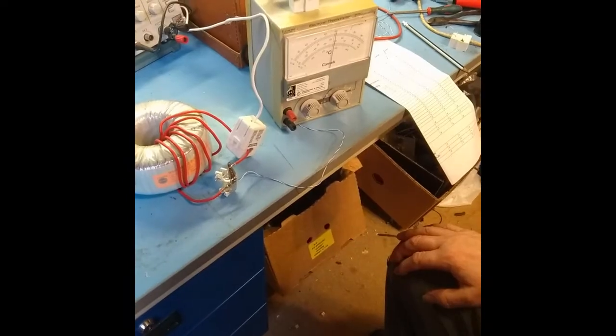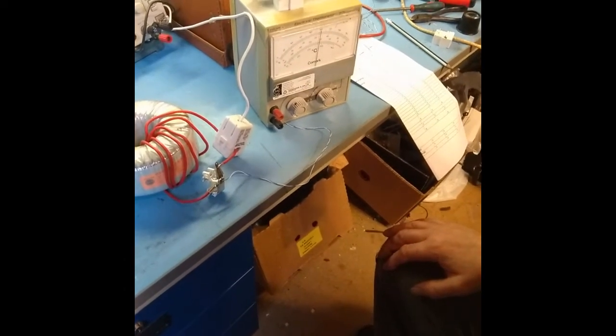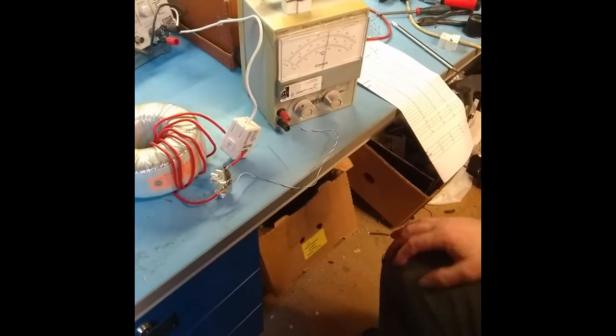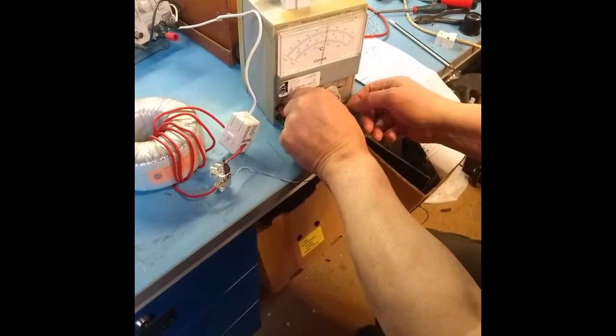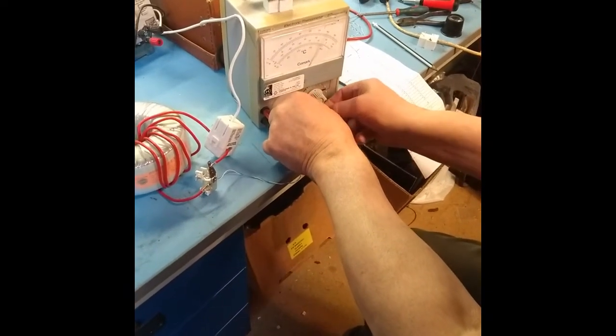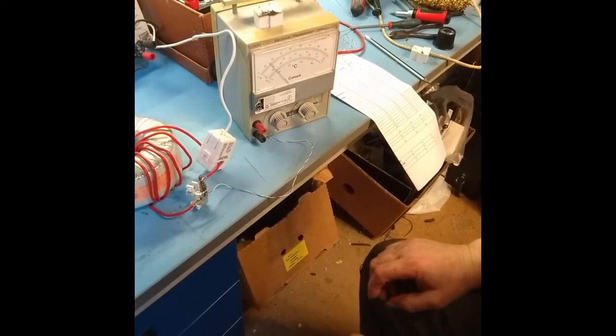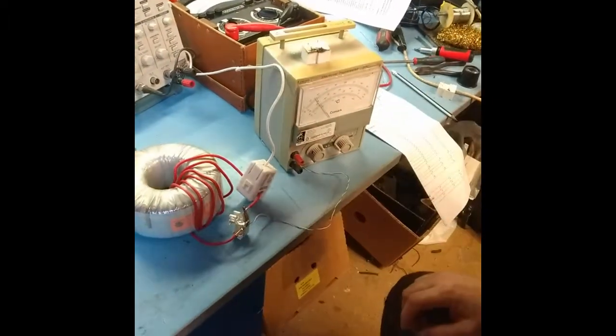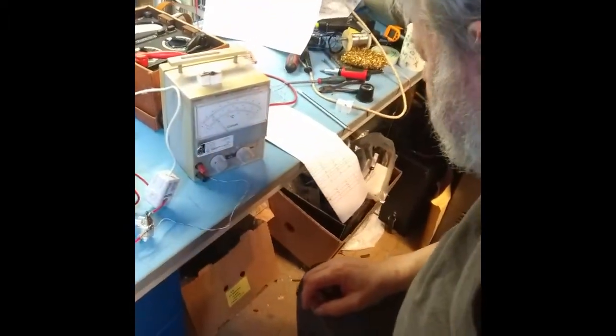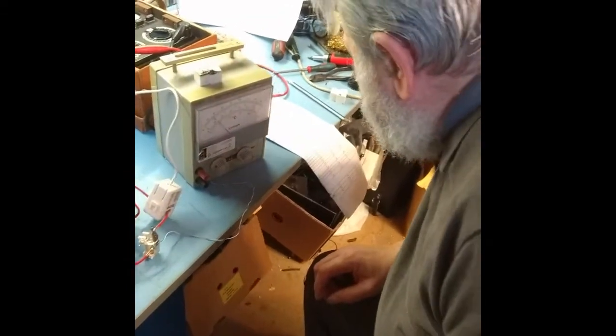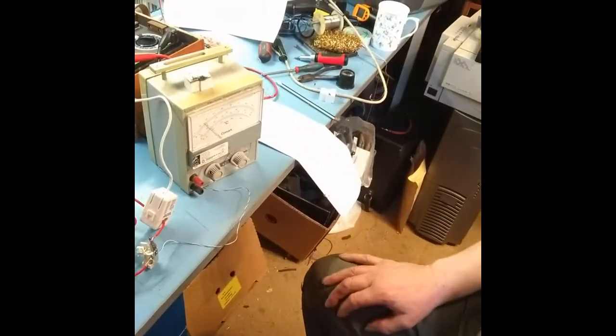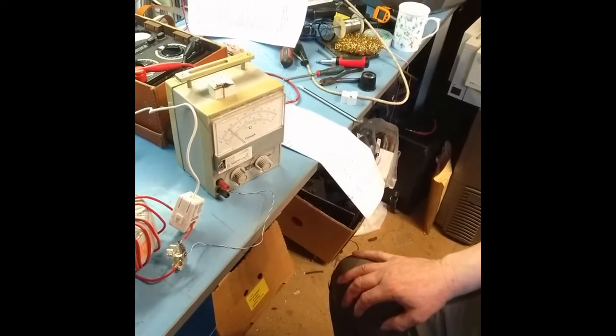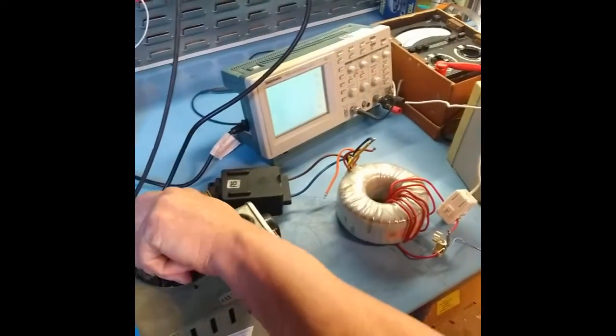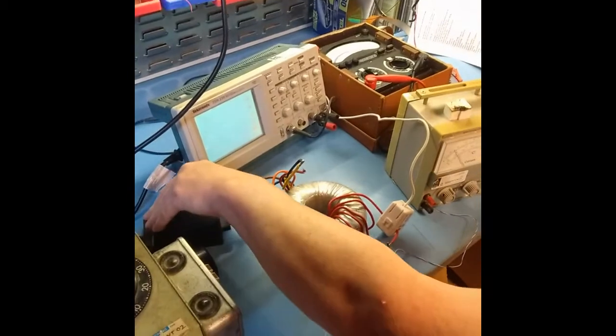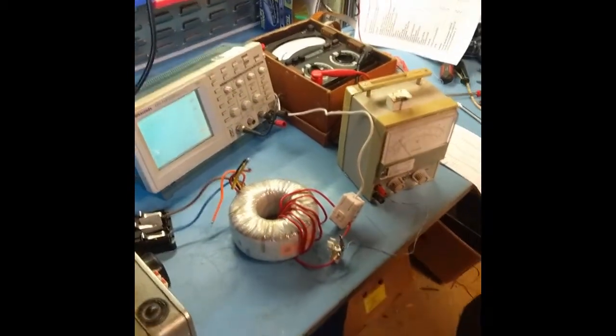It has stabilized at 99 degrees centigrade. And if I compare the ambient, go onto the B scale and go to channel 2, we have 10.5 degrees centigrade. So that's where I'm going to stop. I'm going to turn the current down now to 0 and open the breaker.